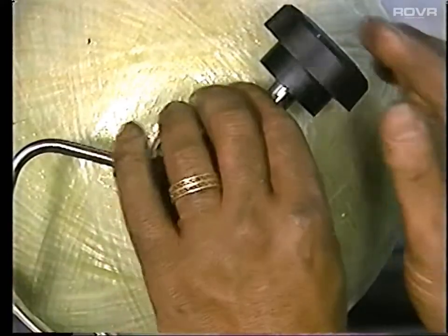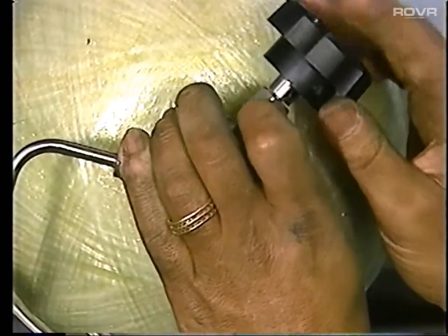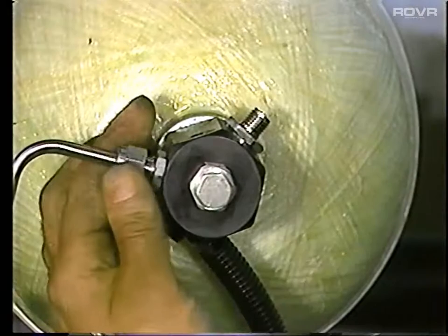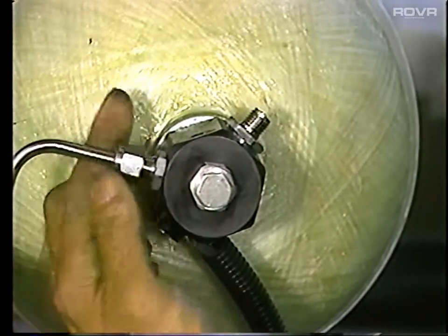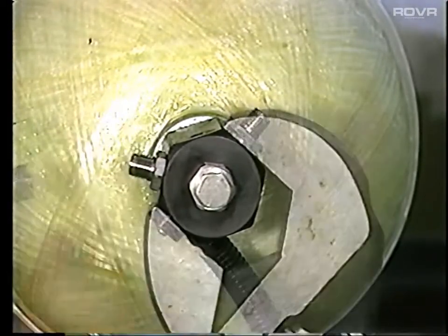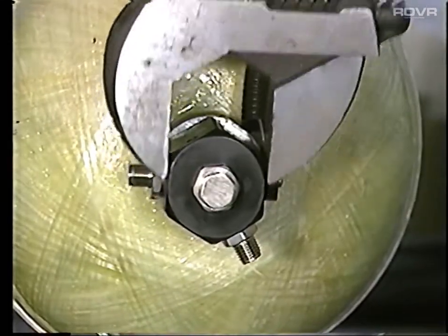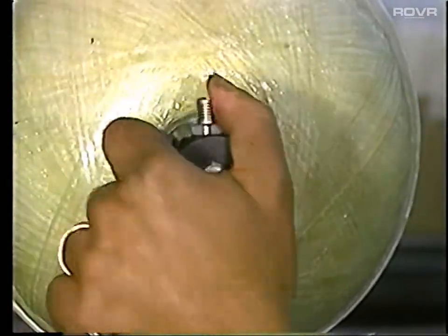Note, as I stated earlier, this tool may occasionally freeze up due to the rapid flow of gas through it. Don't do anything. The valve will thaw and the flow will continue until the tank is empty. After venting, take the truck back into the service area. Remove the Kent-Moore tool. Remove the outlet or feed line from the faulty solenoid. Remove the solenoid valve from the tank, rotating it counterclockwise.